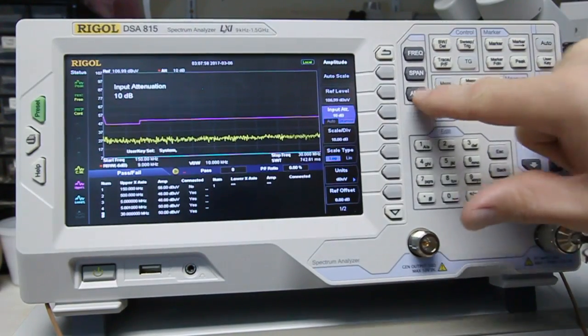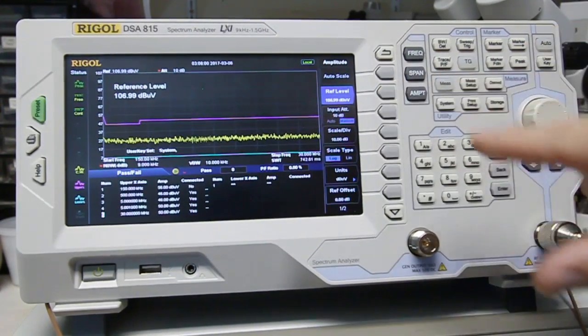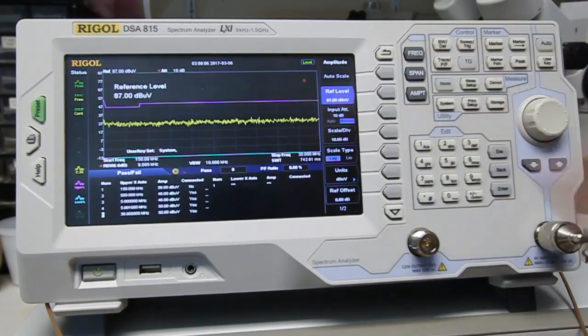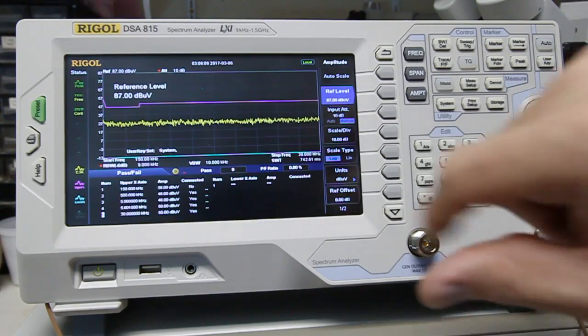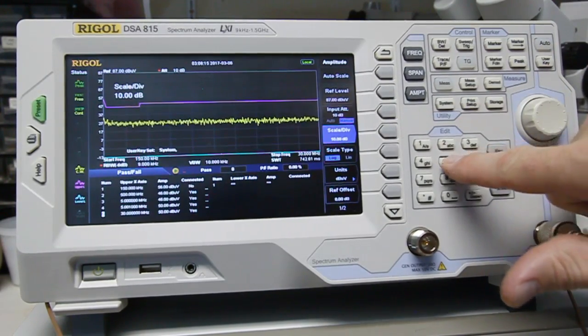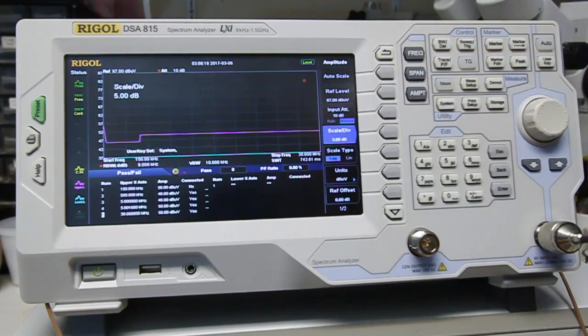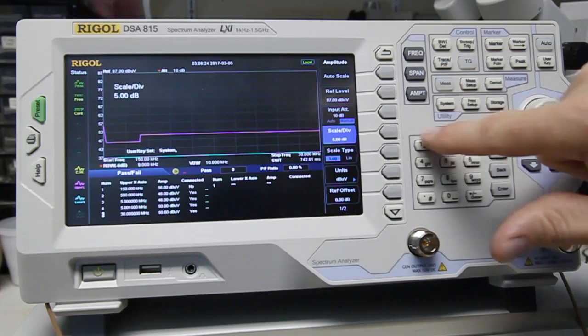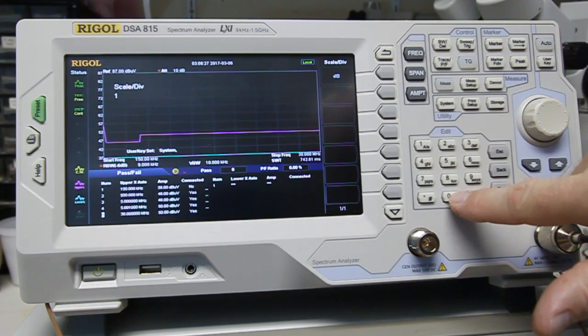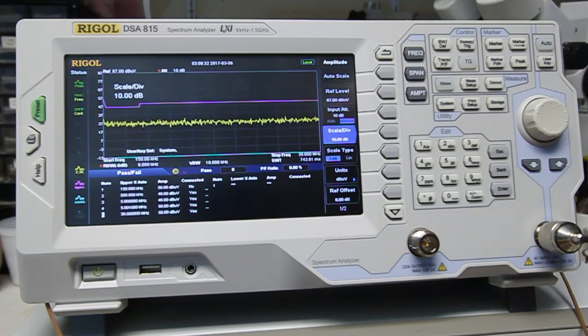Now, to get a little bit better range here, I'm going to change the reference level to something a little lower. I'm going to go to, say, 87 dB microvolts. And I'm going to do 5 dB per division. Oh, that was too much. So let's go back to 10 dB. That should work.